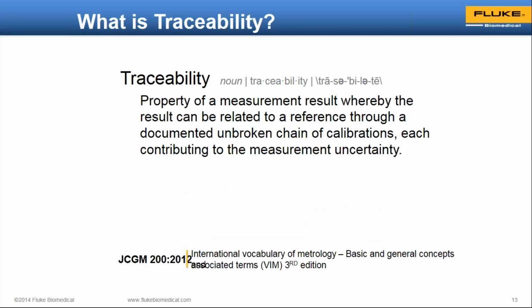Then we want to make sure that our test instrumentation is traceable. Traceable means a property of the measurement result whereby the result can be related to a reference, or a primary or a transfer standard, through a documented and unbroken chain of calibrations that help us be more certain that the test instrument is going to measure correctly and do what it's supposed to do. So traceability is critical, and you need to be sure that whoever you're using to calibrate your test instruments can show you that unbroken chain of traceability for the calibrations of the transfer standards they're using to calibrate your devices.